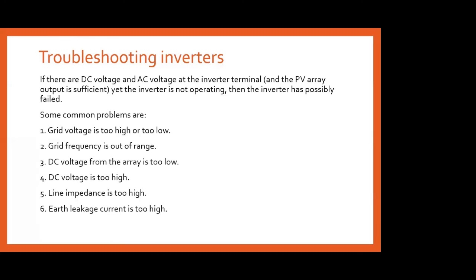Then the third one is if the DC voltage from the array is too low. That is a problem with the array itself, so troubleshooting has to be done starting from the array. Or the DC voltage may be too high. If the DC voltage is too high, there may be a problem from the array itself, and we have to disconnect the array from the inverter immediately so that it will not damage my inverter.